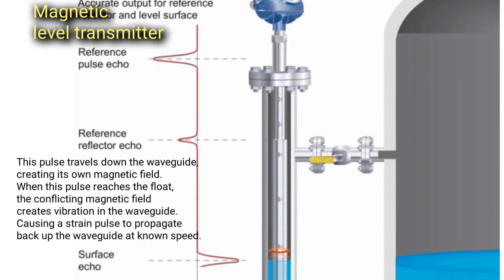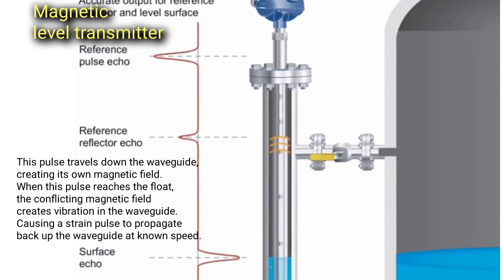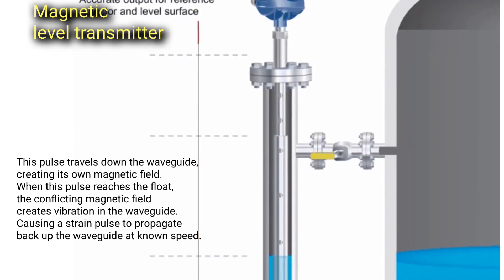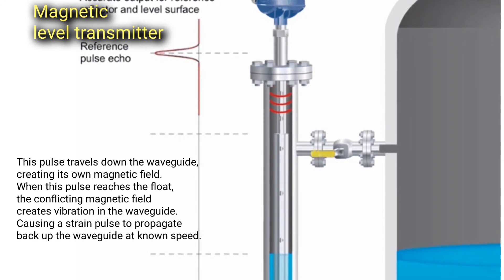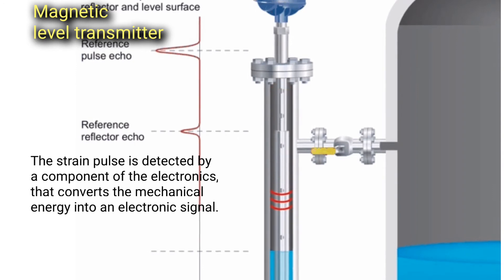This pulse travels down the waveguide, creating its own magnetic field. When this pulse reaches the float, the conflicting magnetic field creates vibration in the waveguide, causing a strain pulse to propagate back up the waveguide at known speed. The strain pulse is detected by a component of the electronics.